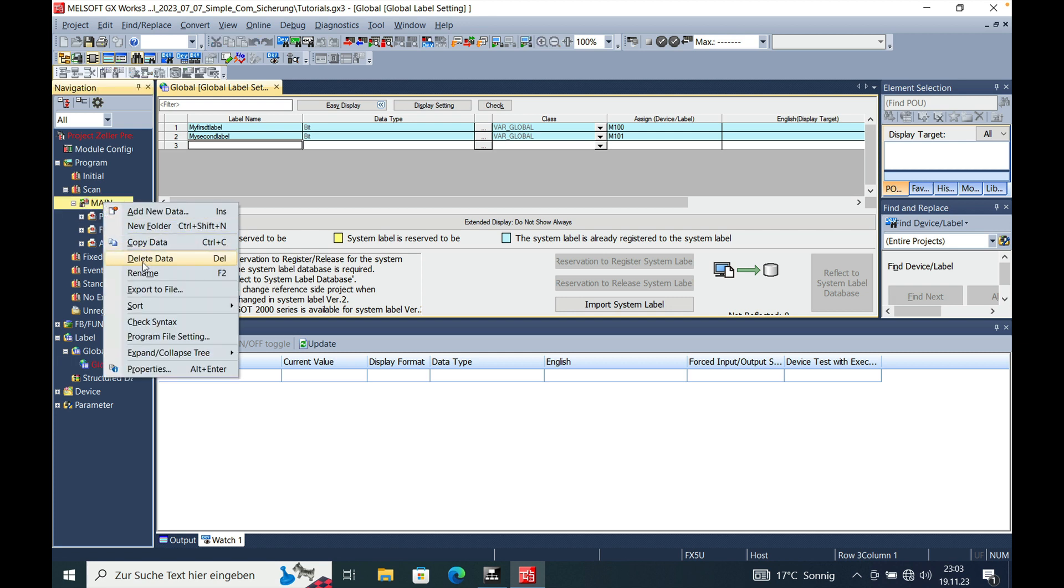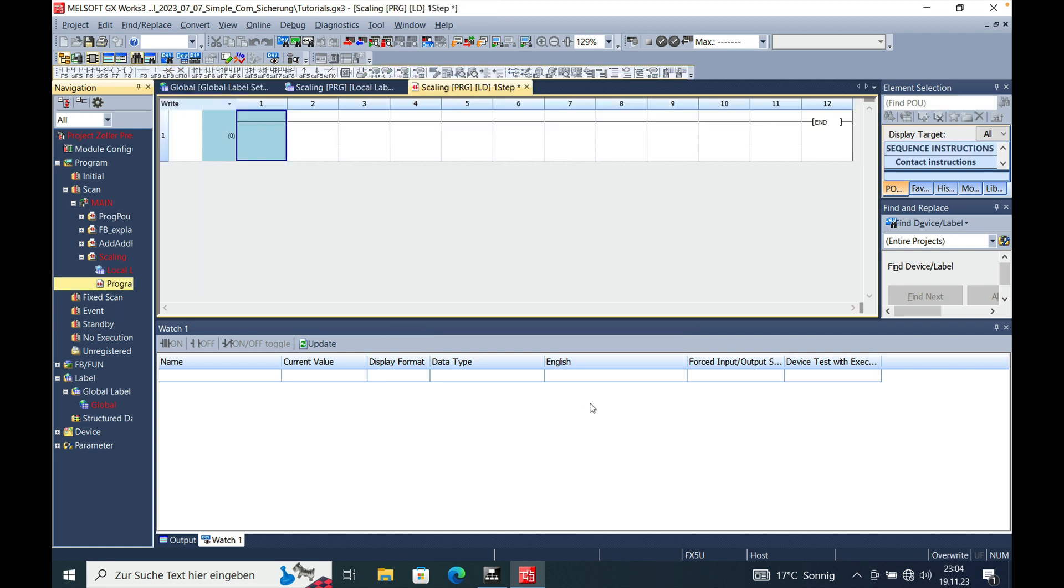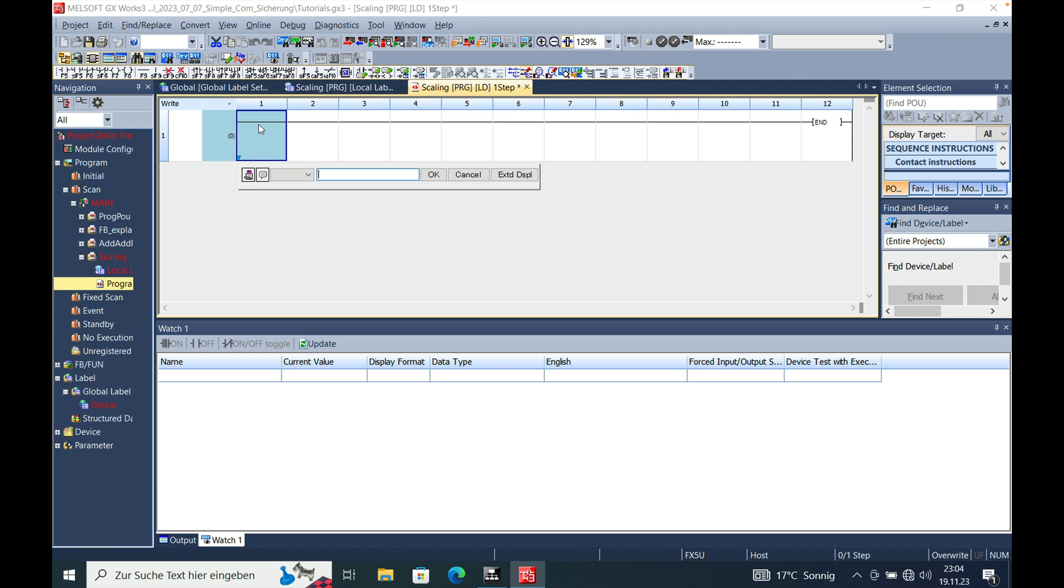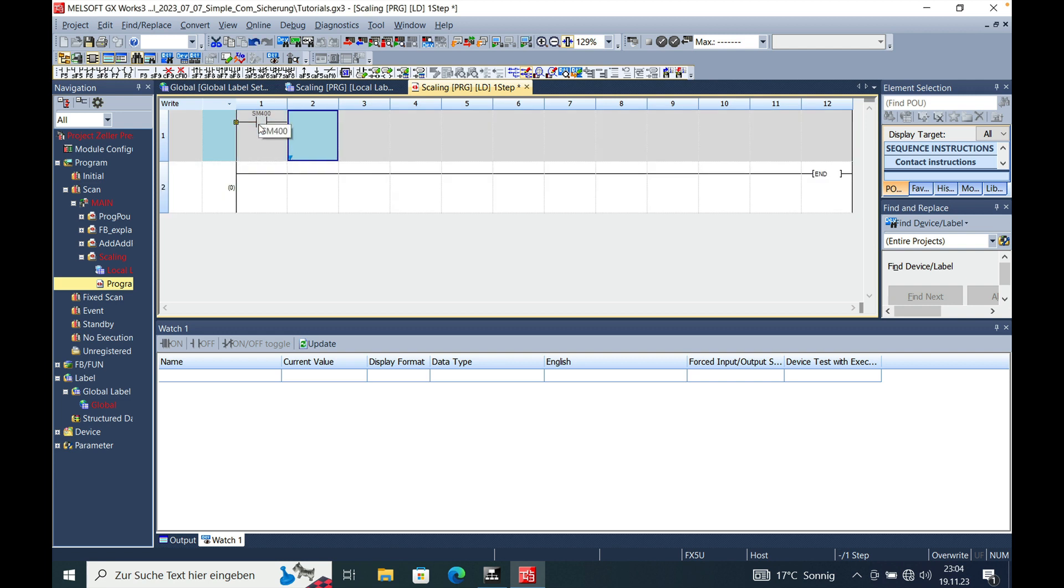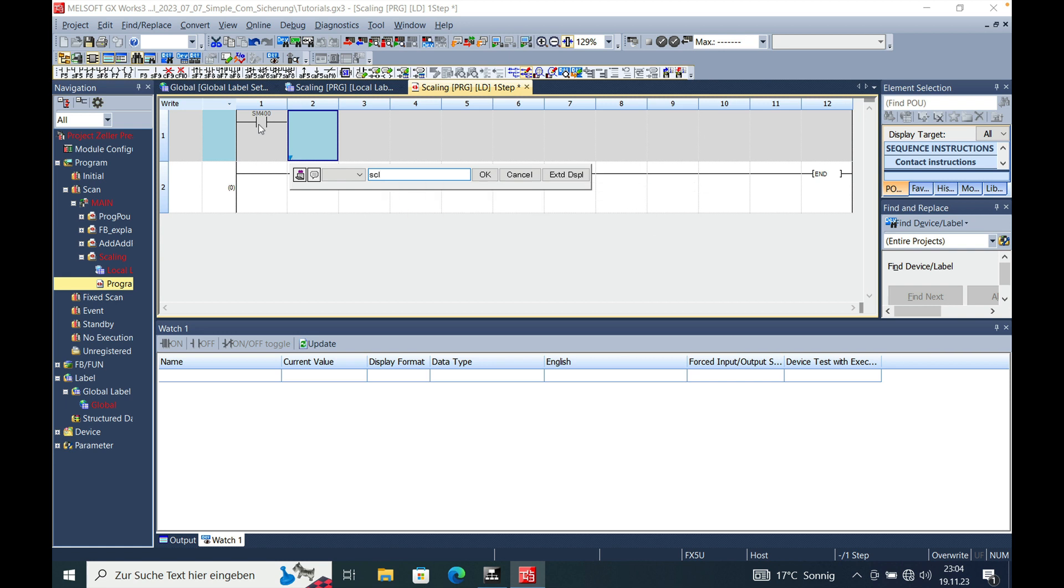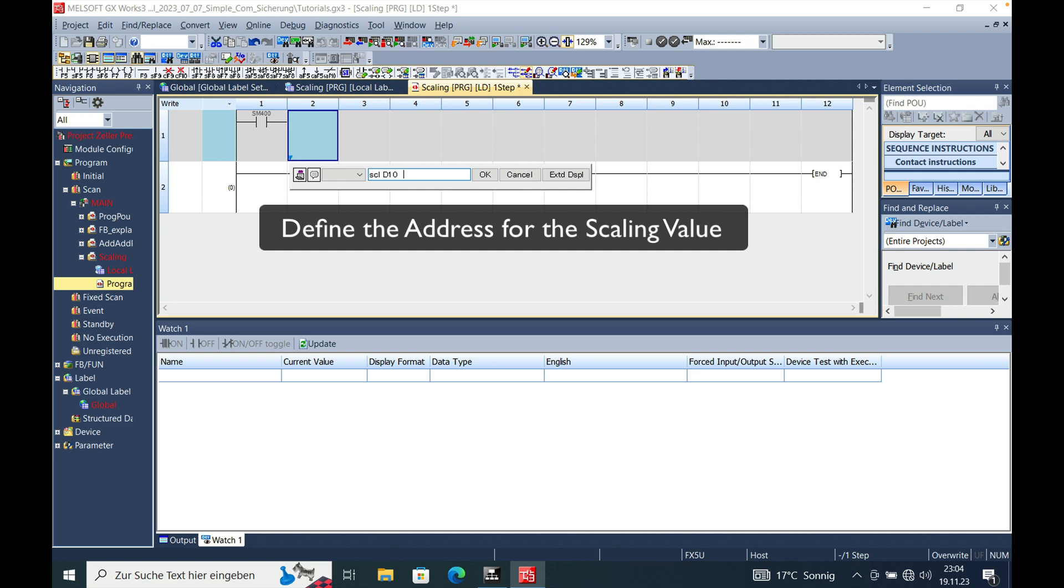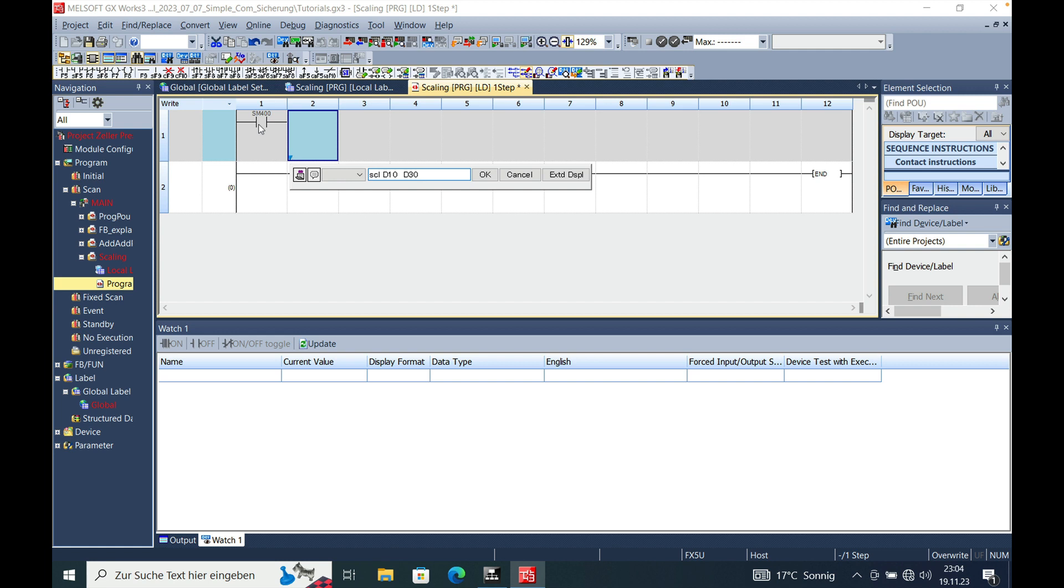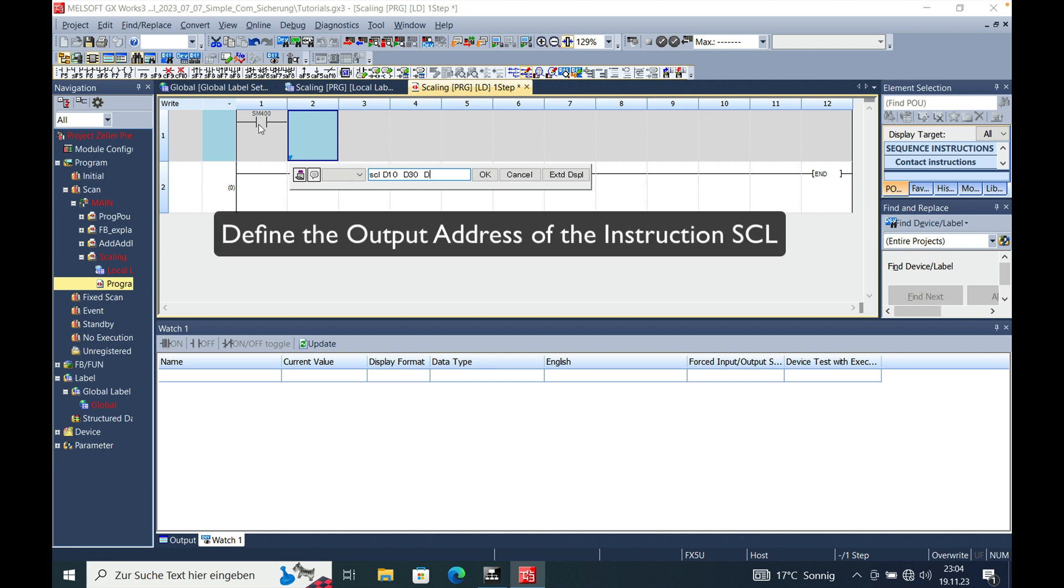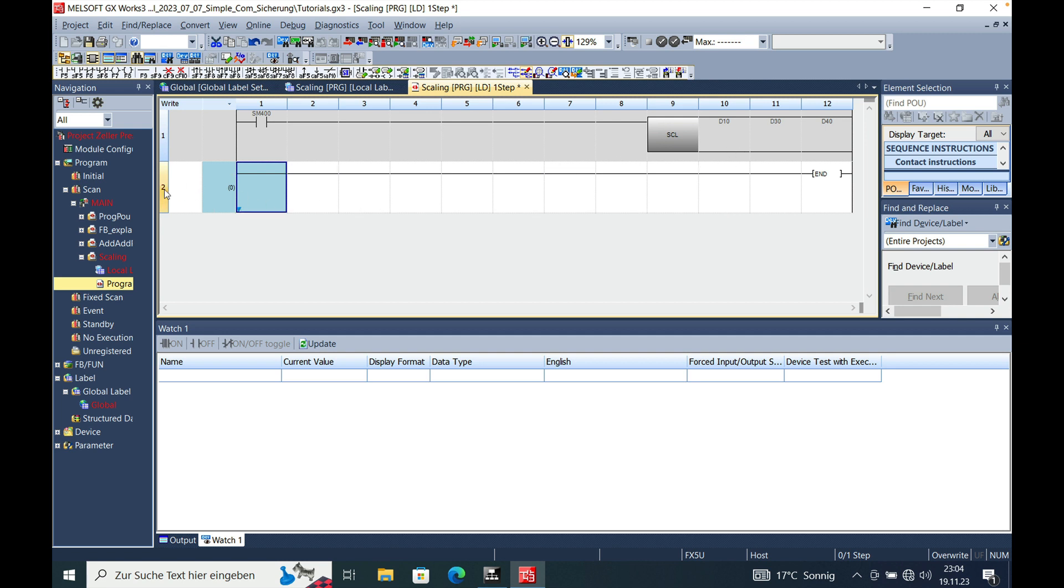First of all, I'm gonna make a new function program block which I just call scaling. And I make this in ladder language. And it's pretty simple. You just put a normally open contact with the SM400 in front of the scaling function that you set here. The scaling function exists of the input word. I call this D10 in this case. And then the scaling values itself which is the D30. And this is split up in 5 words which I will just explain to you. And then the output value which we will call just the D40.